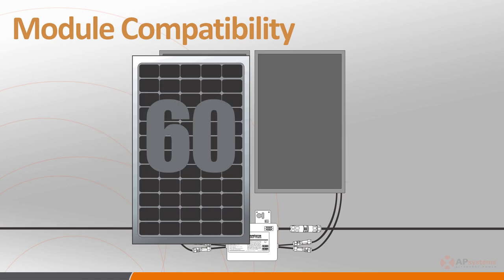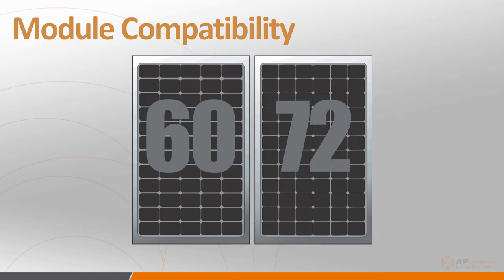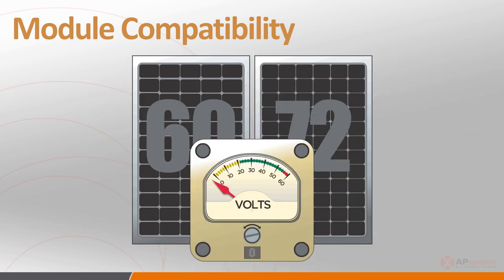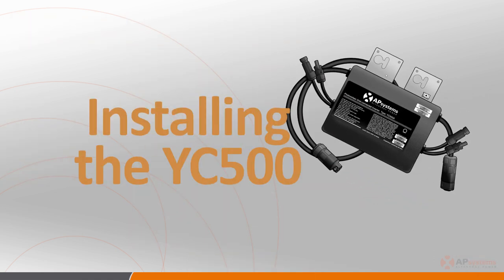The YC500 is compatible with both 60 and 72 cell PV modules, with a voltage range of 16 volts to a maximum of 55 volts continuous. It requires 22 volts to energize. Anything below that voltage level on the input side and the inverter will not power up. Okay, with all the background information out of the way, it's time to start walking through the actual installation procedures.